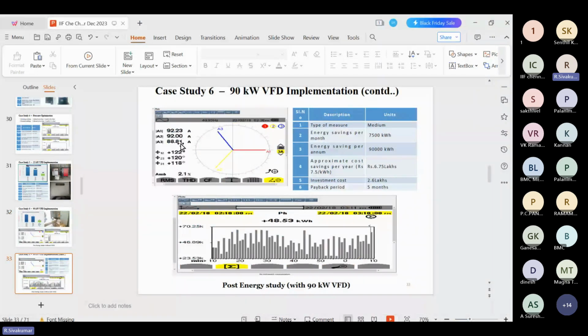So the overall energy saving is almost 90,000 units per year, at the rate of 300 working days. The approximate cost saving is 6.75 lakhs. The investment cost is 2.6 lakhs. The payback period is only 5 months. This project was implemented at the end of 2017, and still the VFD is running in good condition.